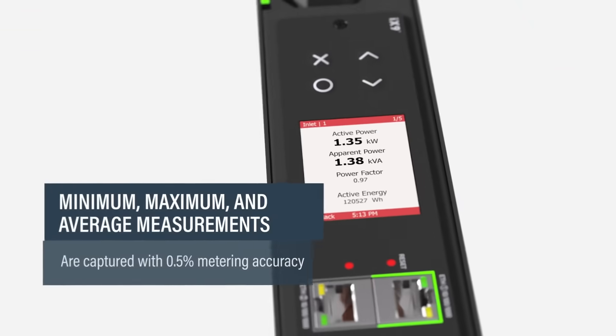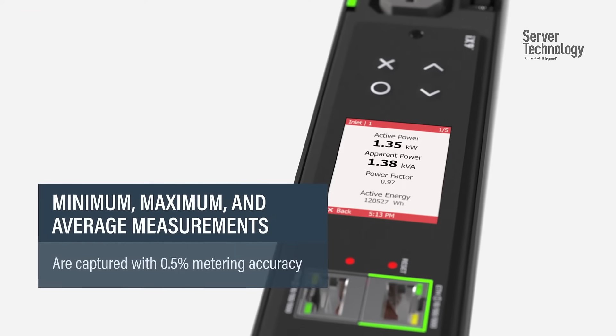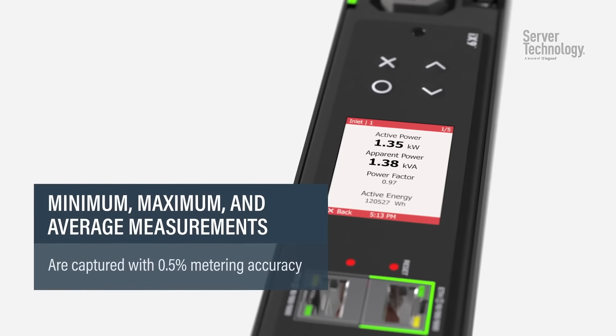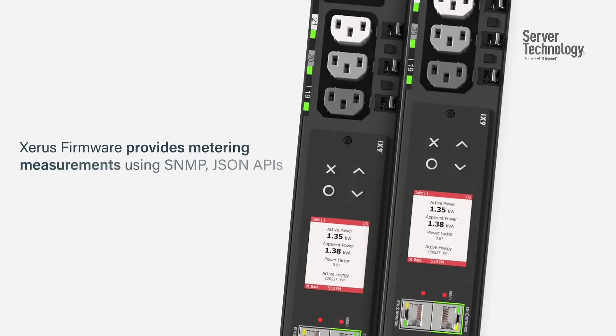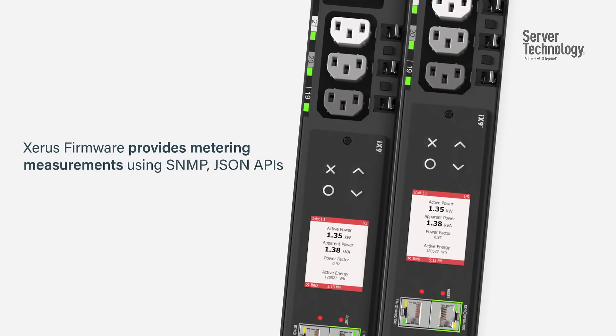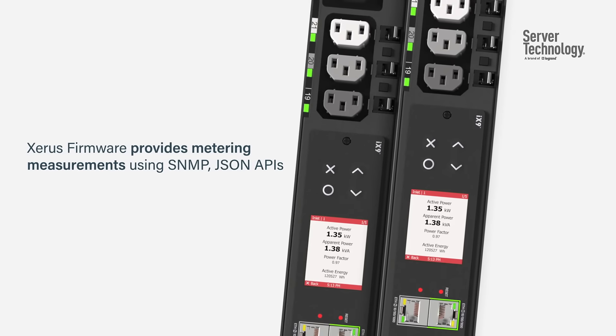Minimum, maximum, and average measurements are captured with 0.5% metering accuracy. Xerus Firmware provides metering measurements using SNMP and JSON APIs in conjunction with DCIM or BMS software.